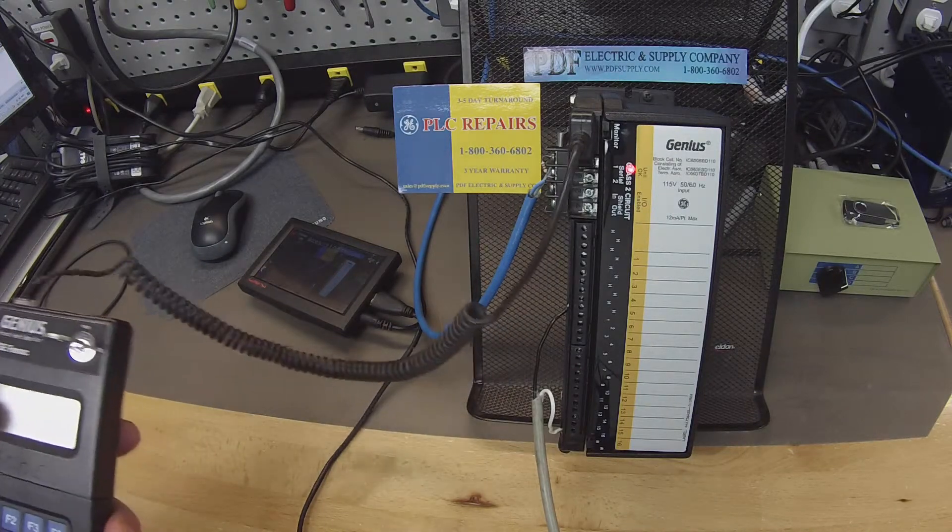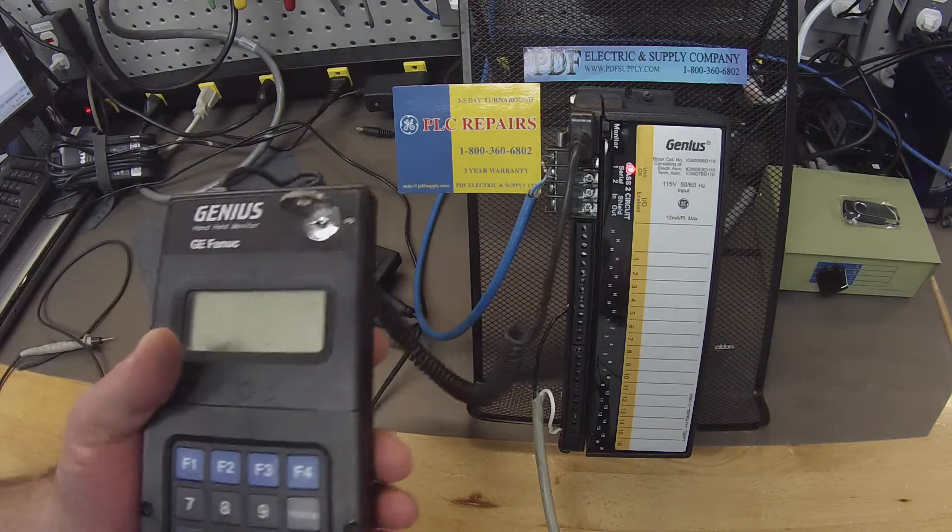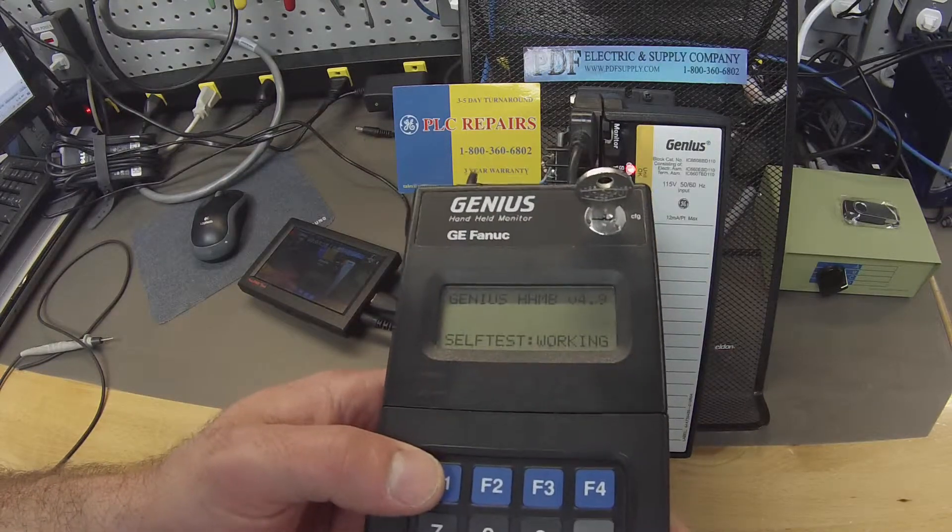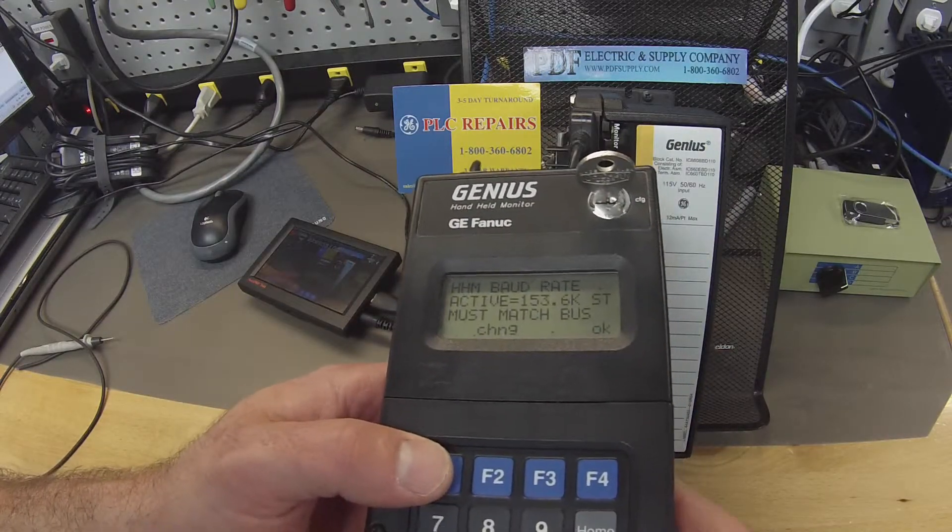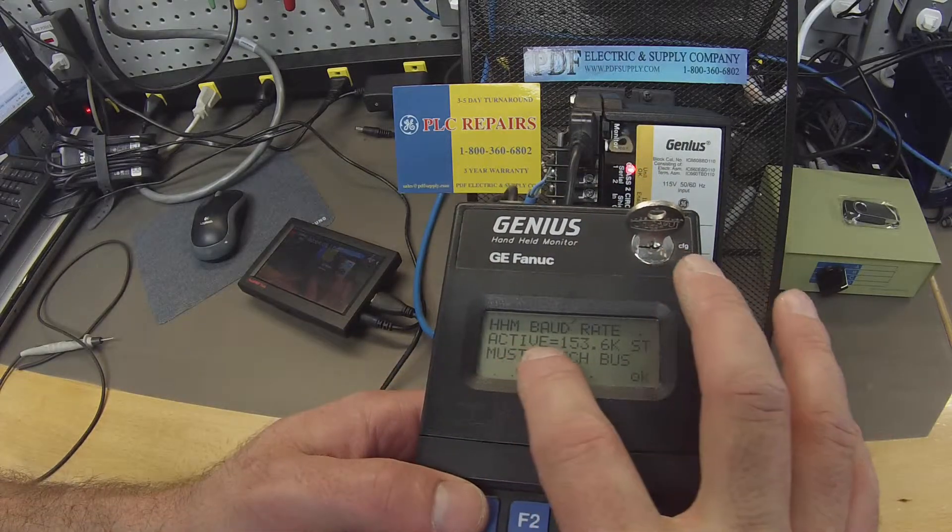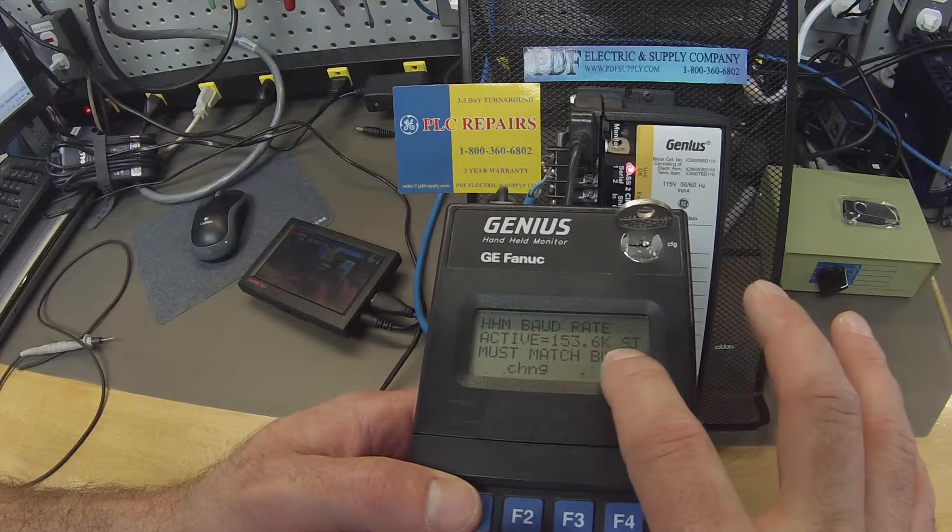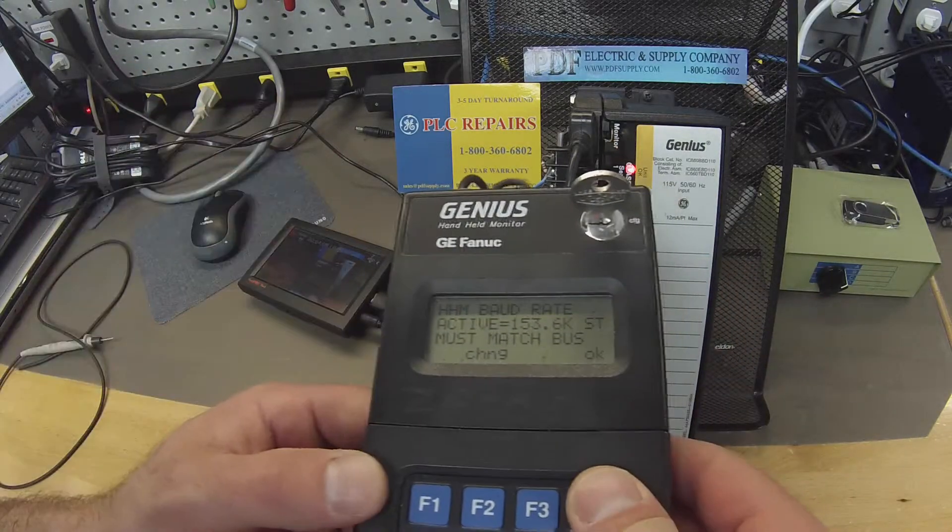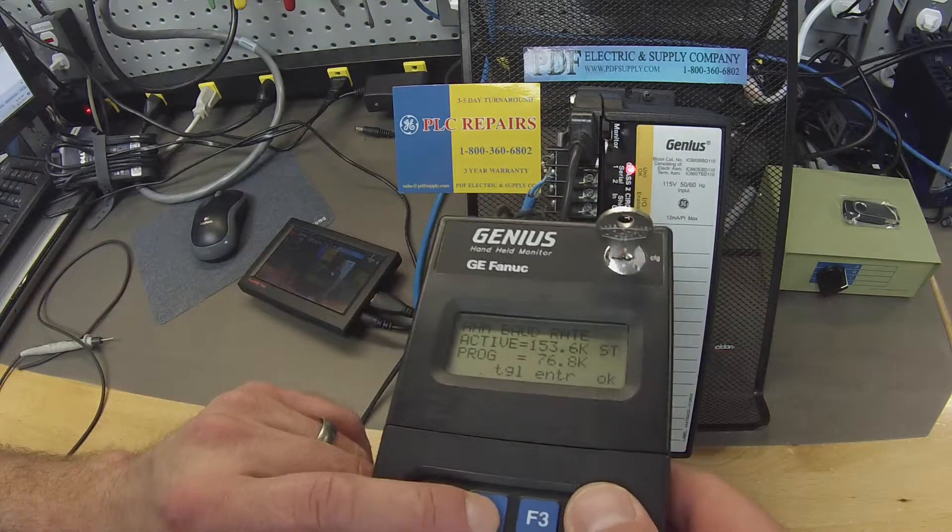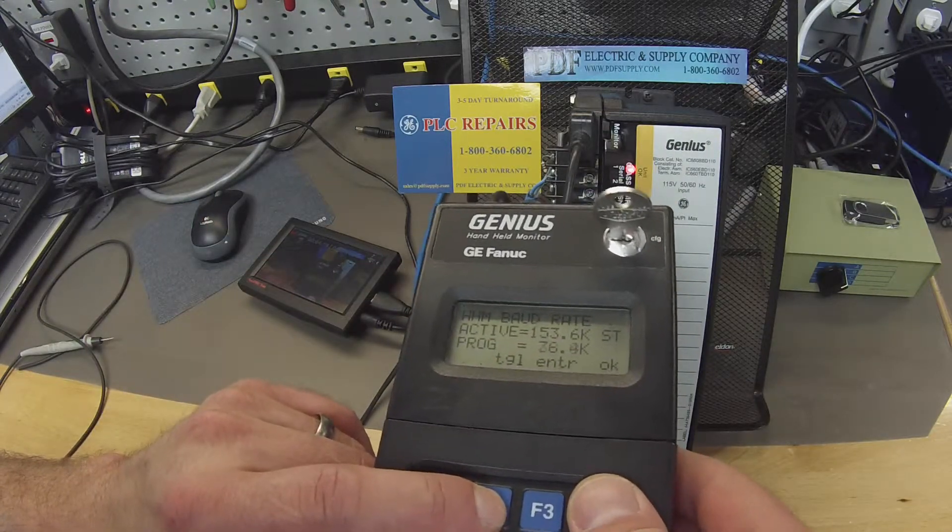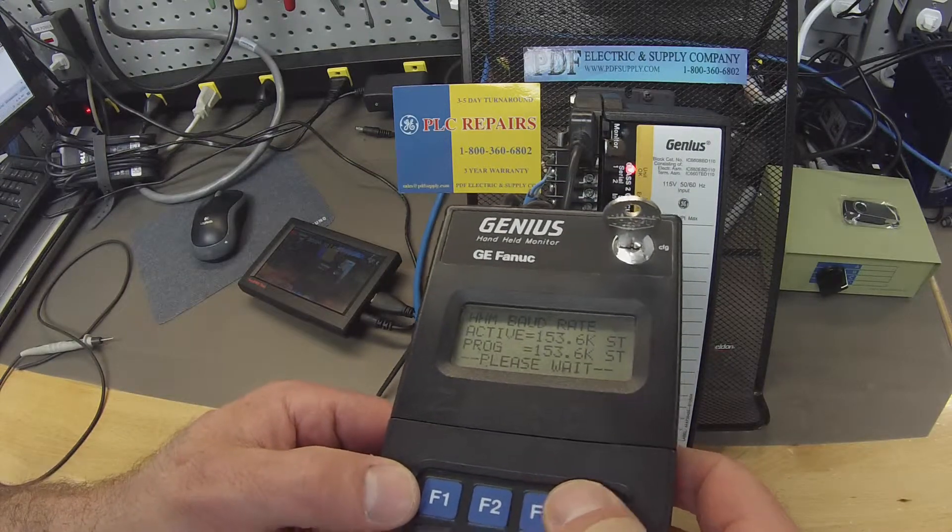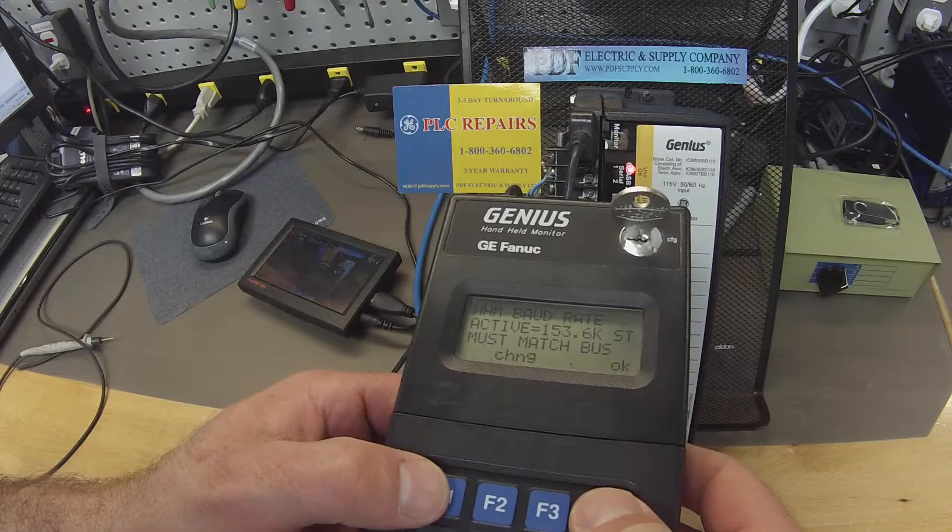Next thing I'm going to do, getting back to the handheld monitor, just so that we're all on the same page, I'm going to turn this on. The default baud rate is 153.6k standard. If you guys are using a different rate, make sure that you change that in here. You can toggle through all the different speeds. Like I said before, we're using the standard rate, 153.6k. I'm going to select OK.